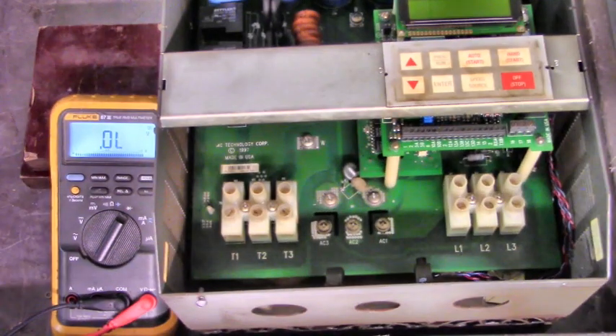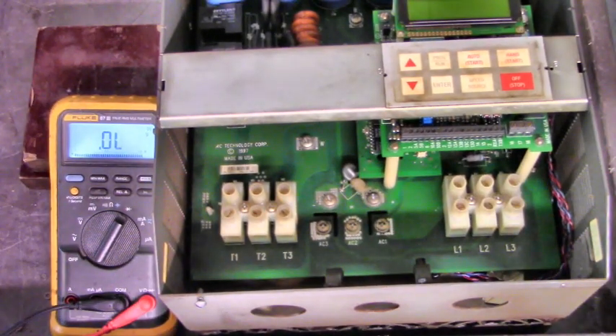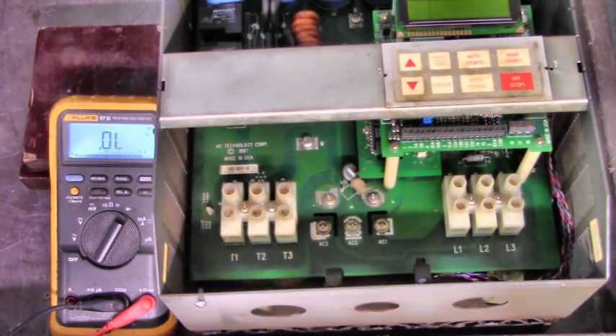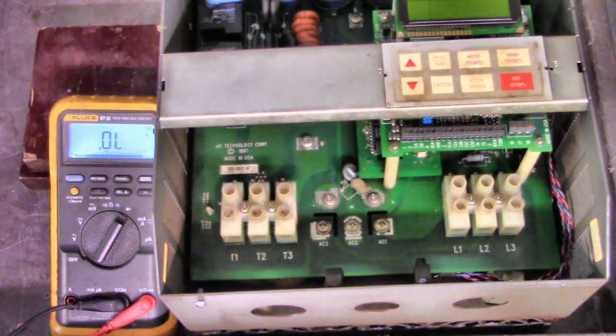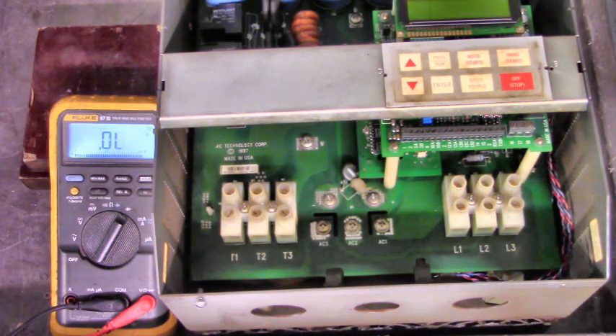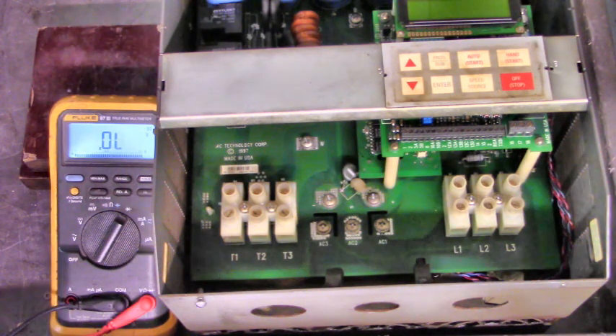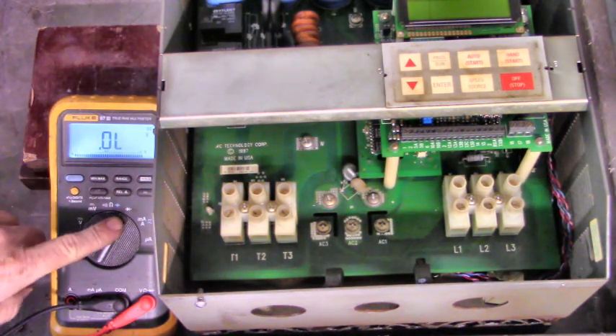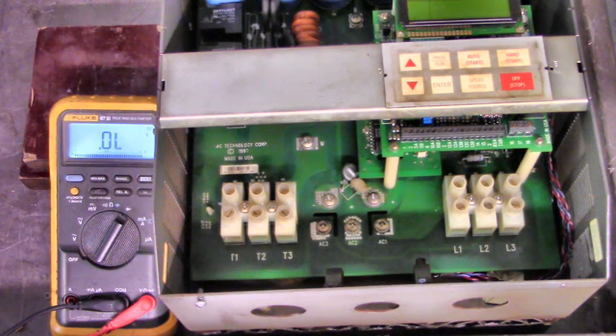Now, before we fire this up, I want to make sure that there's no shorted devices, three-phase bridge or IGBT power module. I've got my meter set to diode test mode.